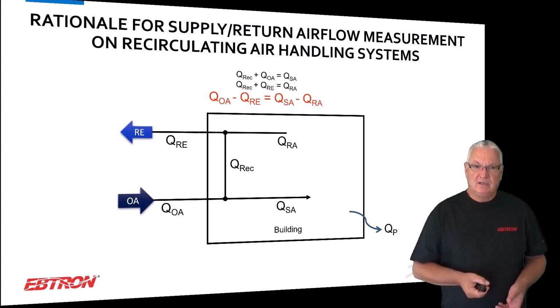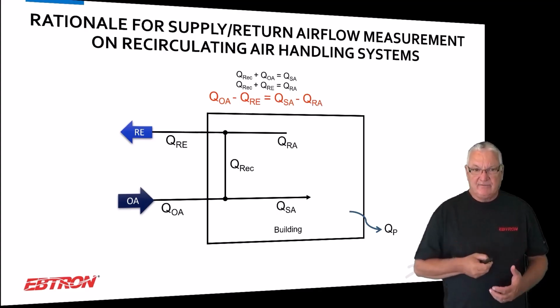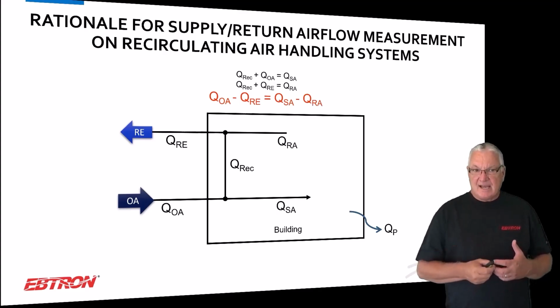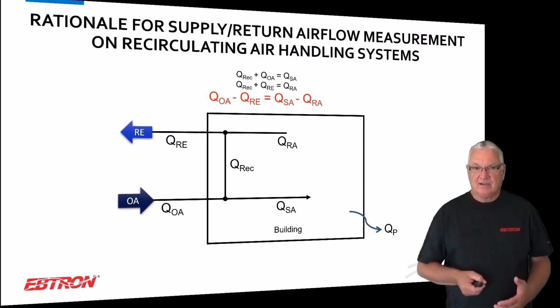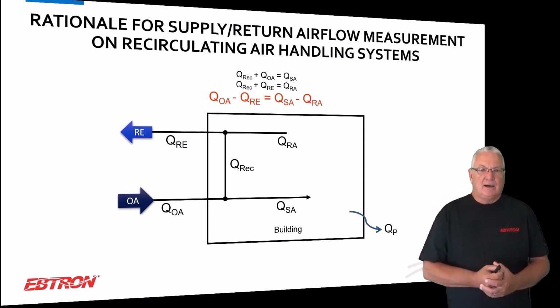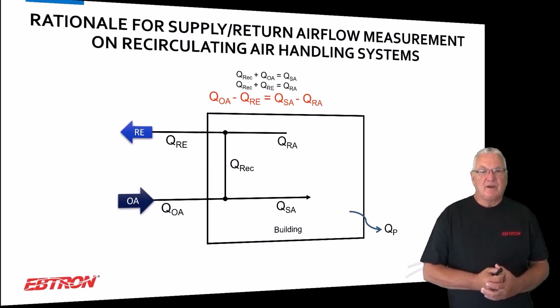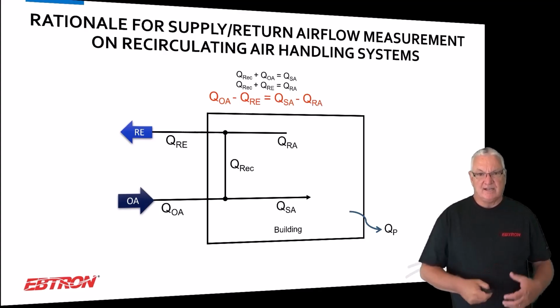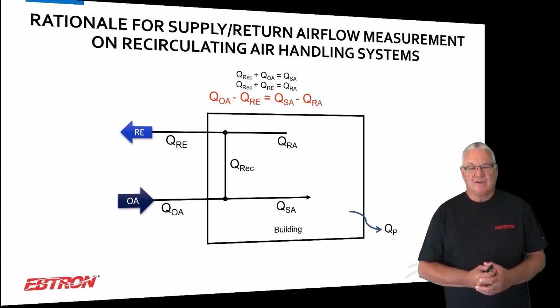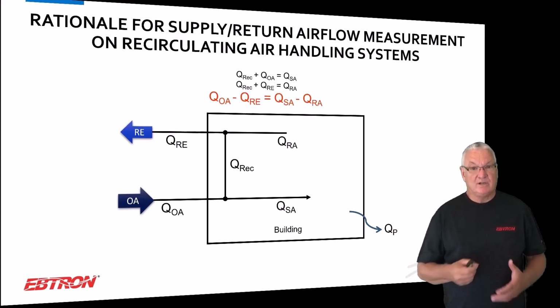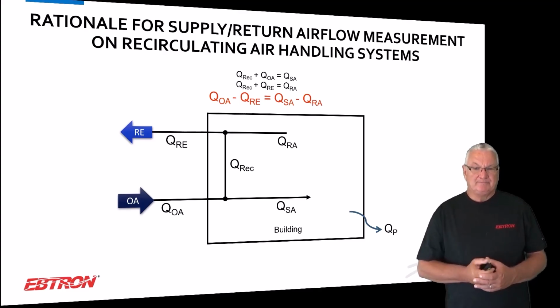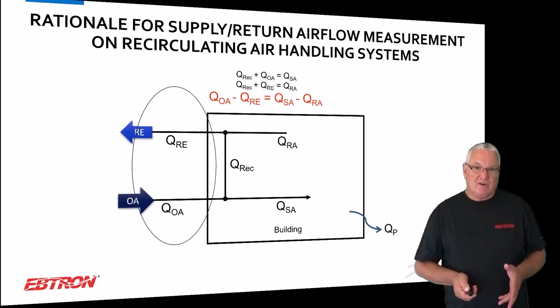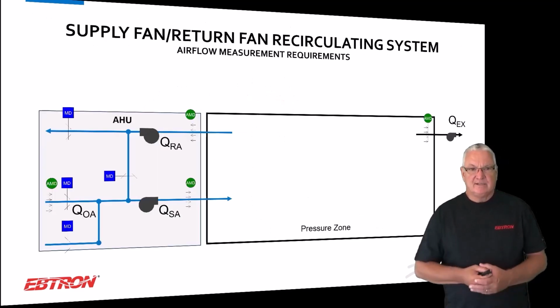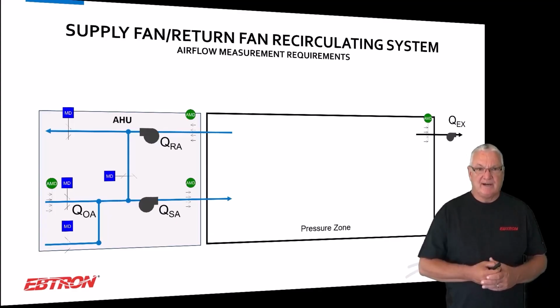So there's no reason to try to measure outside air and relief, which are normally not as accurate a measurement as supply air and return air. So that's why I like to go there. There's also what happens when you go into supply and return air. I'm not really showing it on this slide, but assuming you're using good dampers, you could go 100% recirc, and it's a verification method for the supply and return airflow stations, or even a method of tweaking one of those units if they're not located in a perfect location or as good a location as you would like. So anyhow, that's pretty much where I want to go here. Okay, so that's how we get to where we're going to talk about here.